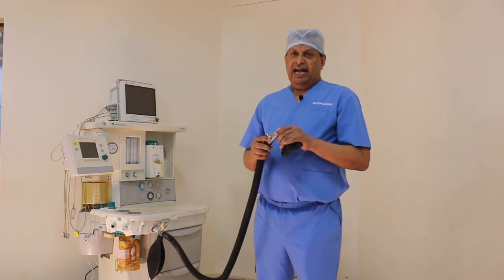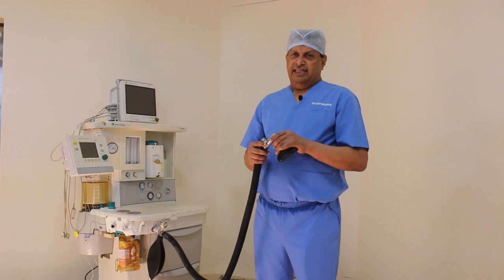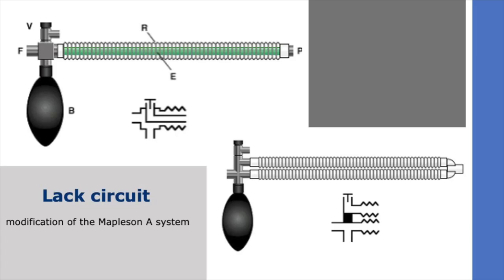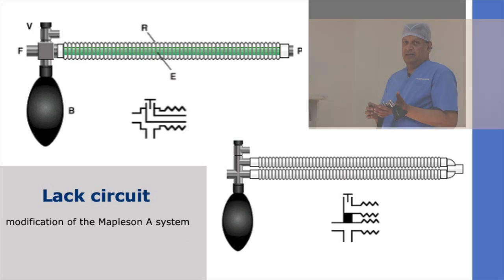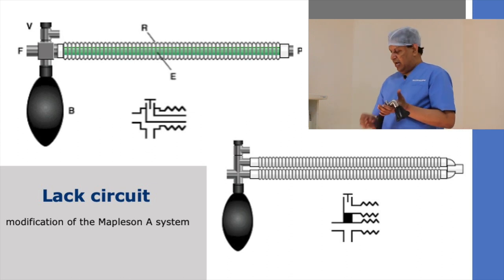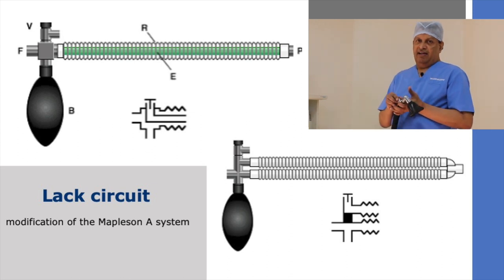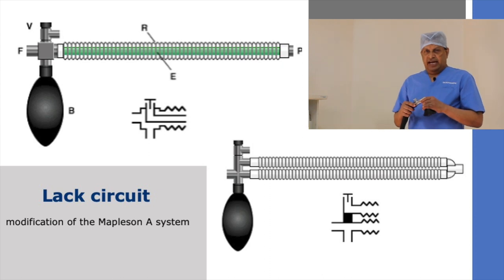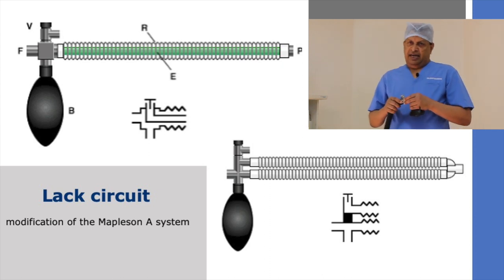To address this, Lack modified the classic Mapleson A system — this is called the Lack system. What he did was move the APL valve from the patient end to the machine end. An additional tube from the patient end connects to the APL valve, so expired gas moves through that tube during expiration and vents out through the APL valve. This can be either a coaxial or parallel arrangement.